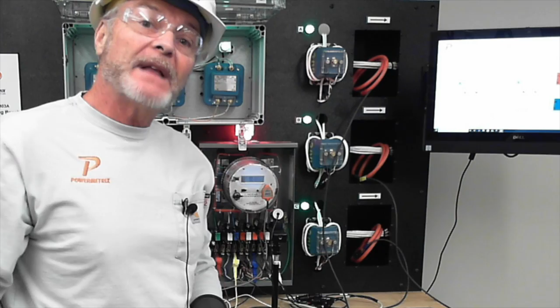So you will need to figure 8 them if you have that application where multiple conductors run through there, trying to save some money on a CT. It means you're going to have to figure 8 that to pull it off. You can't set up another setting to add more CTs - well, you can do more CTs in certain ones, so make sure you look at the service you're setting up. Sometimes you can set it up for more than one CT and just use more than one of these. But if it tells you to figure 8 it, this is what it's talking about.